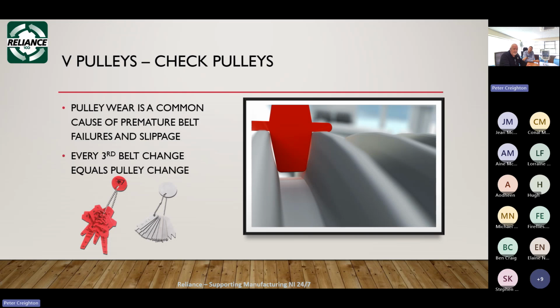A couple of things you need to do when you're setting up your V-belts. You need to actually check that your pulleys are correctly aligned and not worn. And the rule of thumb is that every third belt that you put on, you change your pulleys. People don't do it, and you will not have efficient drives if you don't.